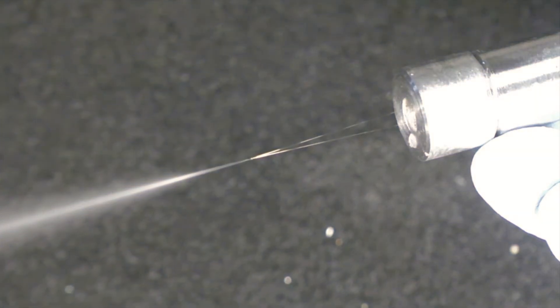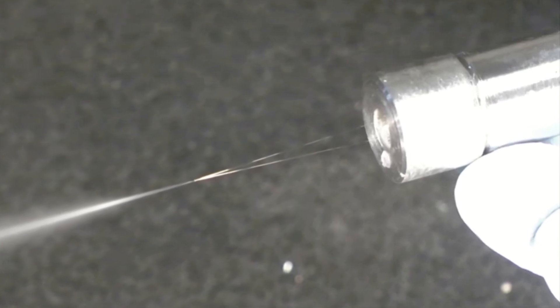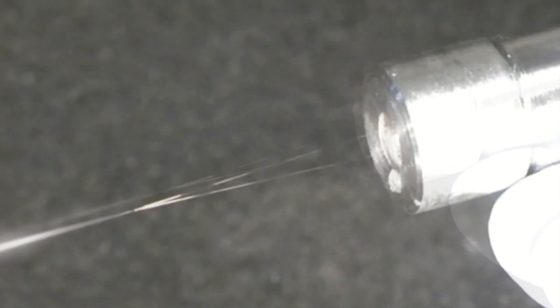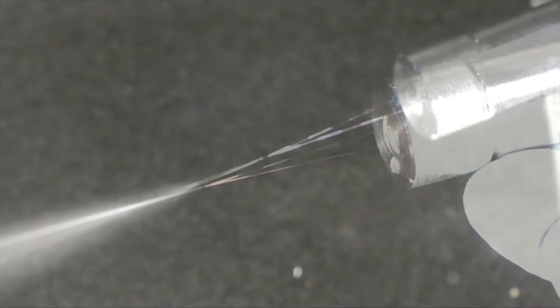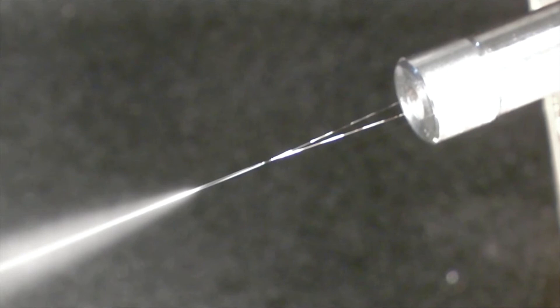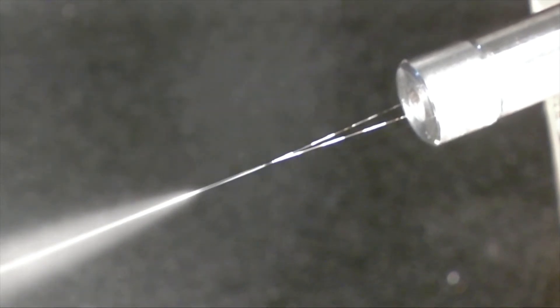This unique technology consists in the generation of two extremely thin convergent high pressure microjets of sterile physiological solution with a minimal flow. These microjets create two distinctive zones: one before the convergence point for transection and one after the convergence point for dissection.